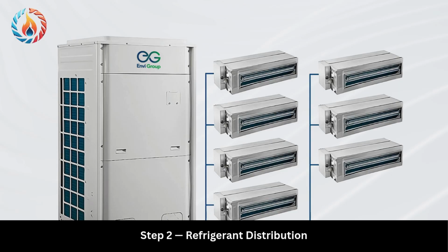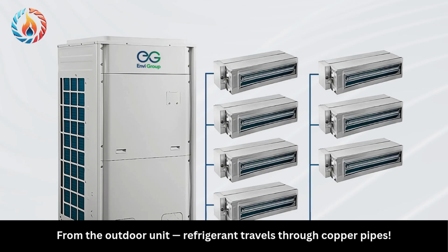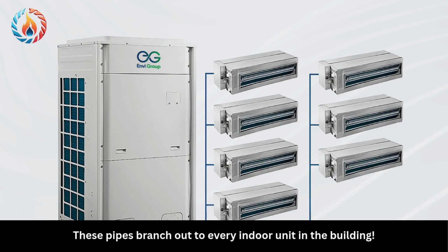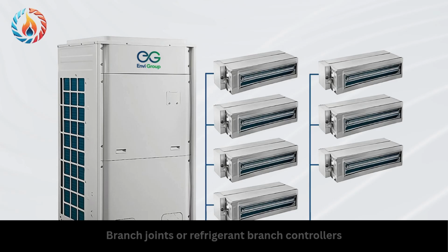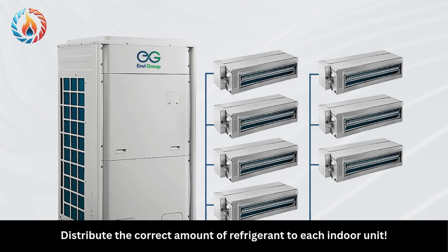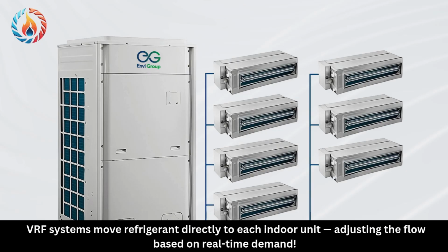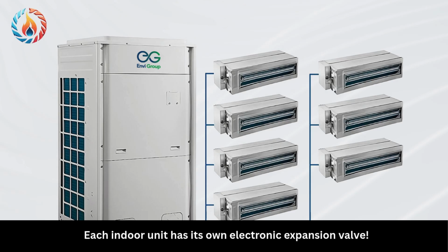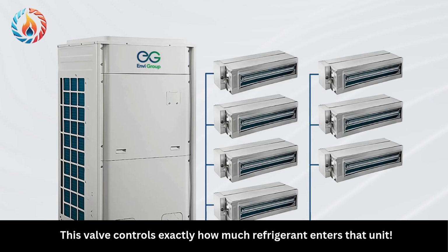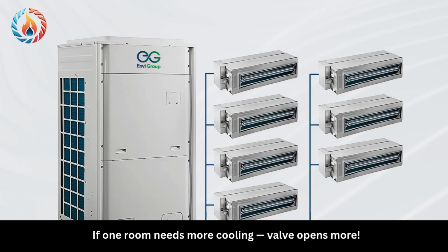Step 2. Refrigerant distribution. From the outdoor unit, refrigerant travels through copper pipes. These pipes branch out to every indoor unit in the building. Branch joints, or refrigerant branch controllers, distribute the correct amount of refrigerant to each indoor unit. Step 3. Indoor units. VRF systems move refrigerant directly to each indoor unit, adjusting the flow based on real-time demand. Each indoor unit has its own electronic expansion valve. This valve controls exactly how much refrigerant enters that unit. If one room needs more cooling, valve opens more. If room is already cool, valve reduces flow. Each room is controlled independently.